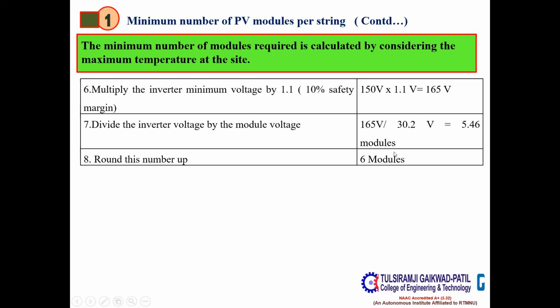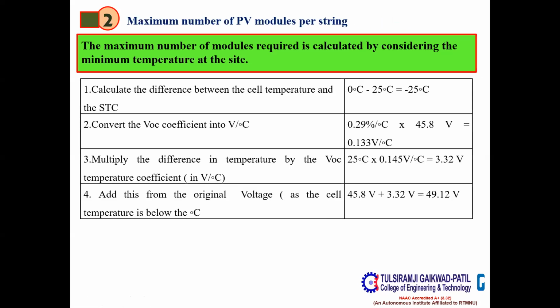Next, please. Next, we will calculate the maximum number of modules. As we have calculated the minimum number of modules, now we need to calculate the maximum number of modules which needs to be connected in series for the problem statement. For this, in extreme cases, 0 degree Celsius is taken as the minimum temperature given in the problem statement. So the temperature difference comes to minus 25 degrees Celsius.